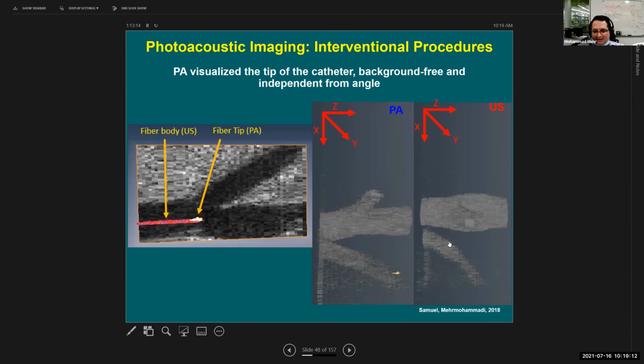When I tilt the catheter to go into, for example, perforating veins, I lose the ultrasound image of it. Why? Because ultrasound works based on pulse echo. If you have something at an angle, your pulse hits that object, but the echo goes out of plane and you don't receive it. So beyond about 35 or 40 degrees, or even less, maybe 25 degrees, we lose ultrasound visibility.